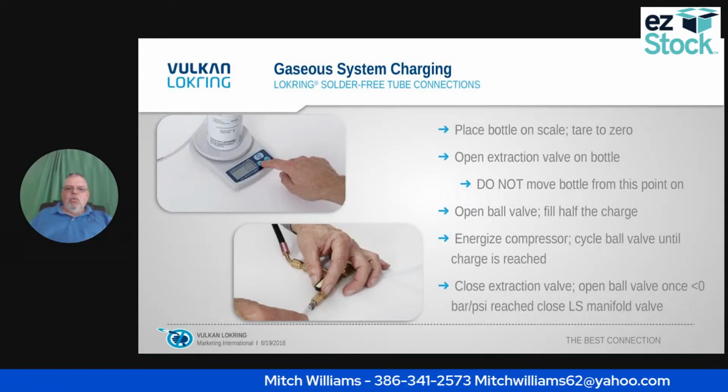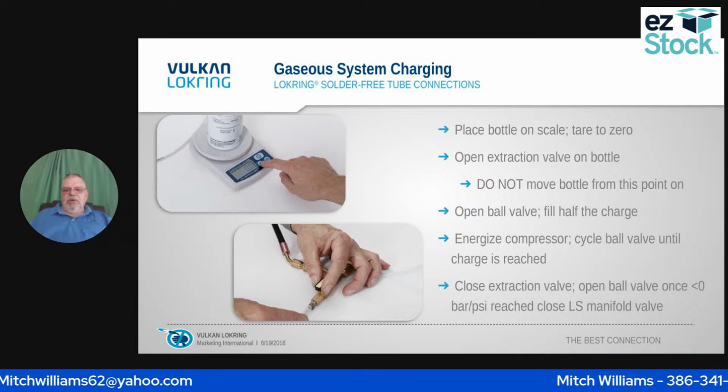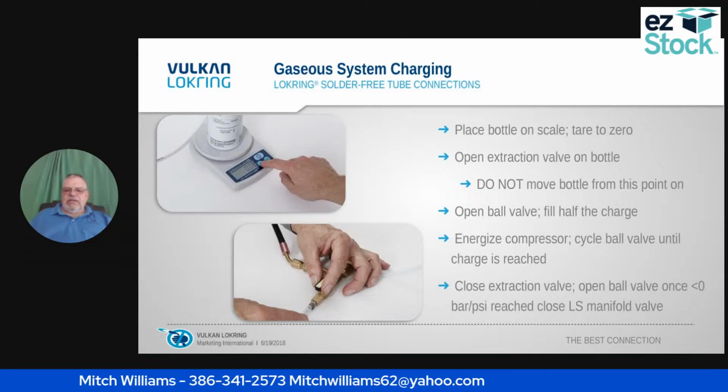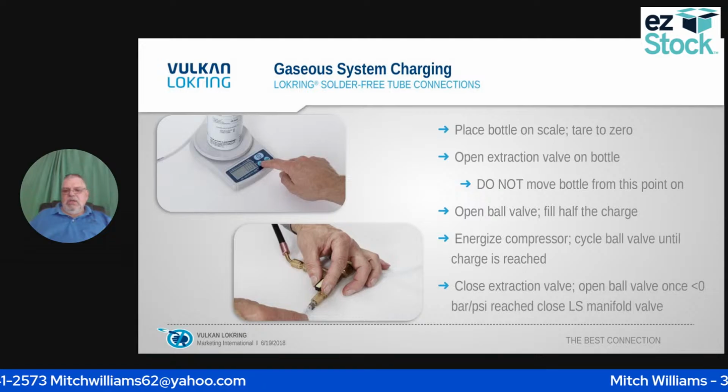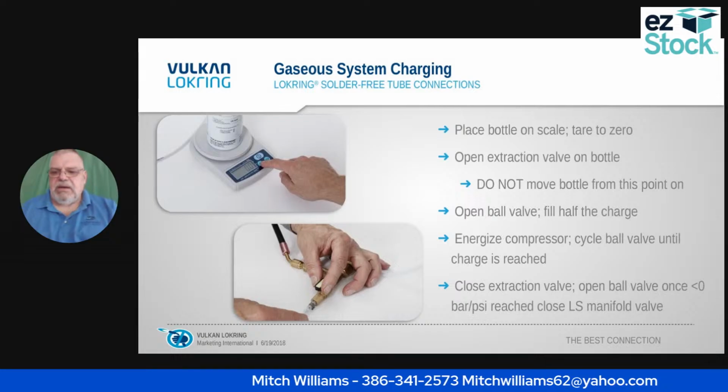Okay, so what am I going to do? I'm going to open the ball valve. I'm going to fill half the charge, energize the compressor, then cycle the ball valve until I get the correct charge into the unit. Then I'm going to close the extraction valve. I'm going to open the ball valve once less than 0 PSI is reached. Then I'm going to close the low side manifold valve.